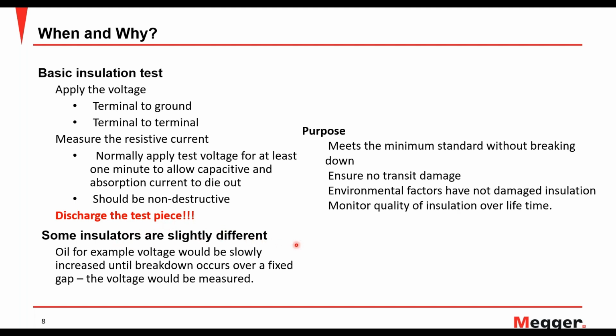Some insulators are slightly different than the others. For example, with oil you would have a slow increase in voltage until breakdown occurs over a fixed gap, and the voltage would be measured. If you have seen an oil breakdown voltage test, you are basically filling up a vessel with oil, and then you have your two electrodes separated by a gap of 1 mm, 2 mm, 3 mm, depending on what kind of oil test you are doing.